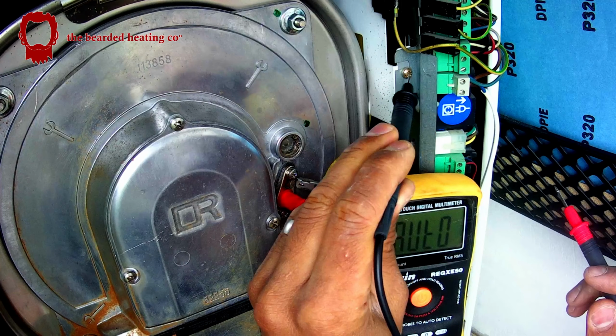But because it's not rectifying, I do think it might be the ignition transformer, this one over here, so we'll have a look at that in a second. These electrodes are only 2 years old - when I did the service in 2019, the way I service is that if it's my first time servicing a boiler and there's a maintenance kit available, I'll use the complete maintenance kit to make sure I've done everything I possibly can to keep the boiler going. So as part of the maintenance kit, it gets a new ignition electrode, which is what I've already replaced. So that goes back in there.